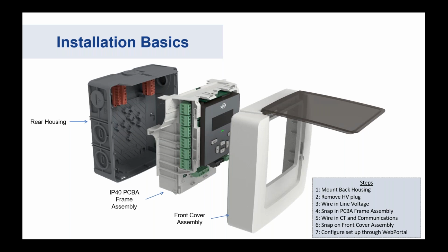You'd snap in the PCBA frame assembly. That's the brains of the meter. That'll cover up those voltage inputs, as well as then you can land your CT wiring and all your communications, and then slap the cover on for the front to seal off the installation, and then begin collecting data on your BAS or energy management software.